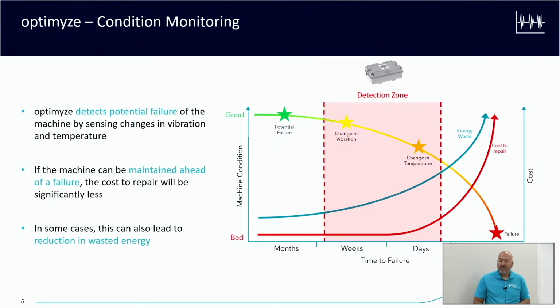And on top of that, you can see the blue and red lines going across the chart here. So the blue line is just showing, as we let a problem continue to get worse and worse, or components start to deteriorate more and more, it becomes less efficient. It's consuming more energy now. And also, as we let a problem get worse and worse, typically the cost to repair it becomes more as well. So just some more benefits or cost savings in capturing these things ahead of time is you're going to save yourself quite a bit of money just from an efficiency and cost standpoint on the maintenance side. And we also want to do it while they're deteriorating, where with preventative maintenance, we may find ourselves changing out parts that are completely fine and we're throwing away completely good components.